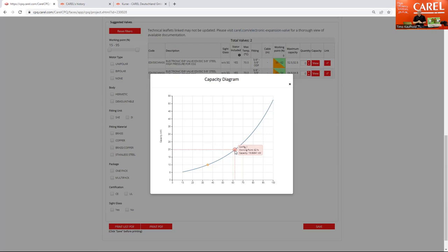The next time you have a service, you can check it and see what is happening. If your valve starts to open more and more, going out of range, and is at 100% opening, you know something is really, really wrong. Maybe I'm missing refrigerant in the system, or I have a totally different problem.